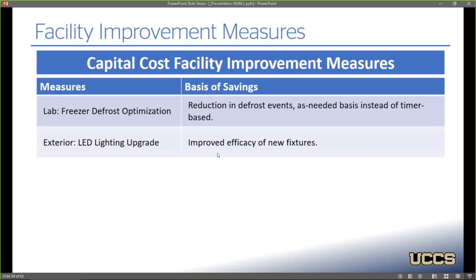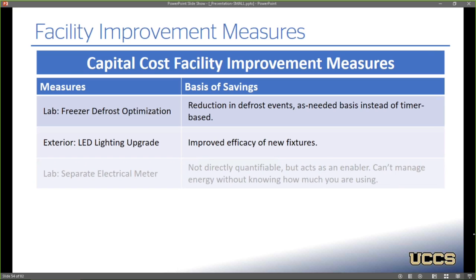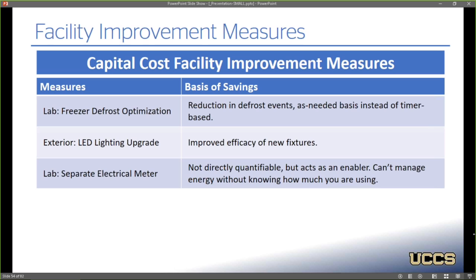On the exterior lighting, they could go to LED lighting, on the basis of savings from the improved efficacy of the fixtures, and they could also look at installing a separate electrical meter at the lab. And the savings there wouldn't be directly quantifiable, but knowing how much energy you use allows you to notice irregularities and can lead to indirect savings.